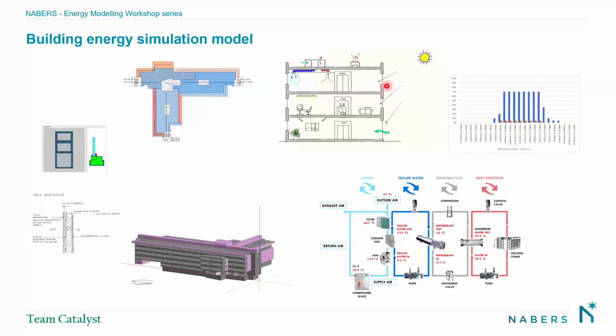Then, as we said, there is a heat gain or heat loss because of the construction of opaque building elements. That decides how the temperature on the outside and the sunshine that's falling on that opaque construction comes into the space or gets lost from the space if it's a cold ambient condition, and how slowly or how fast it does. That's determined by both the U value and those material properties which decide how thermal mass in the building works. Okay. Then we have a series of loads on the inside. The three that we normally consider in office buildings are people loads, lighting loads, and equipment loads. And I'm sure you all know how that works in the NCC.